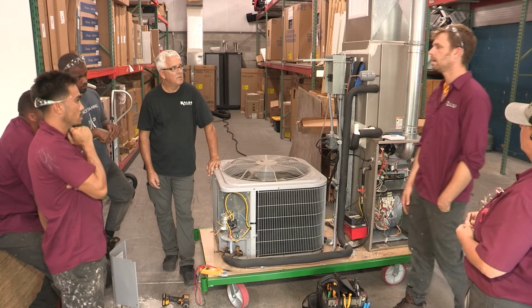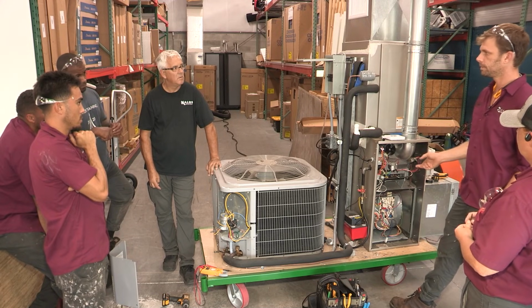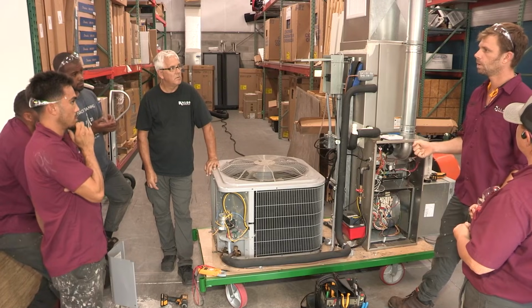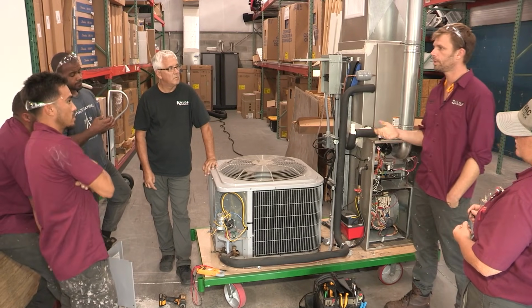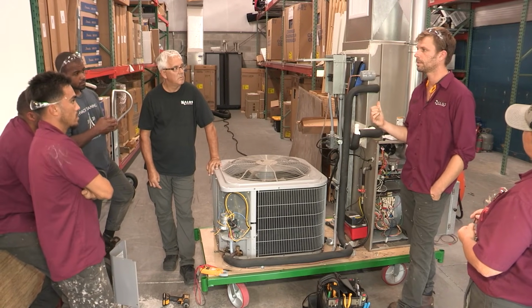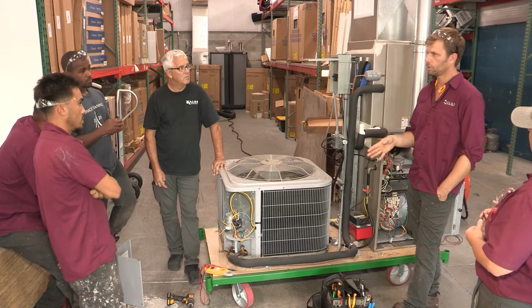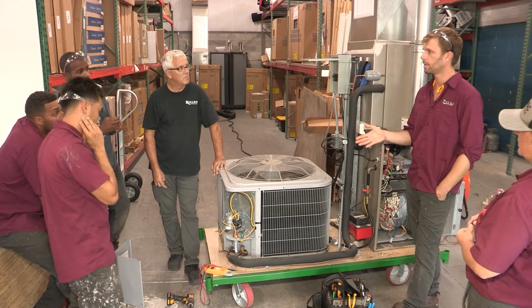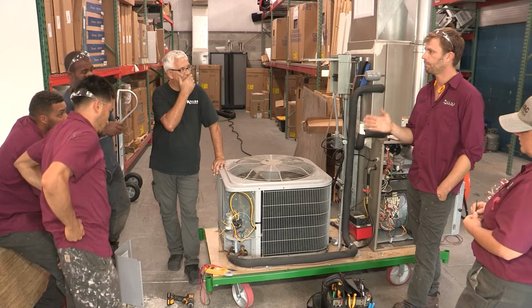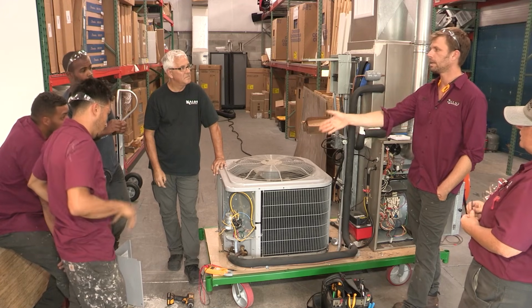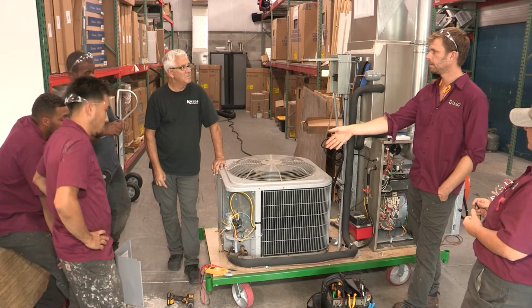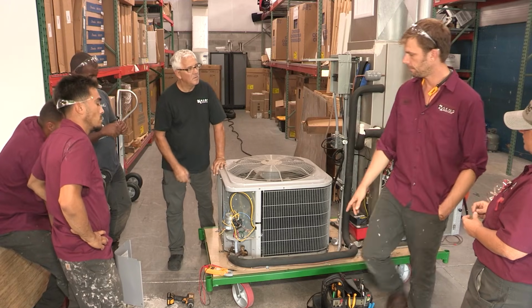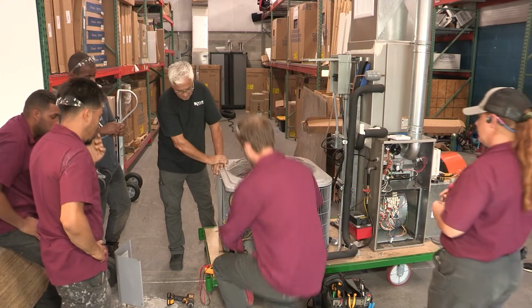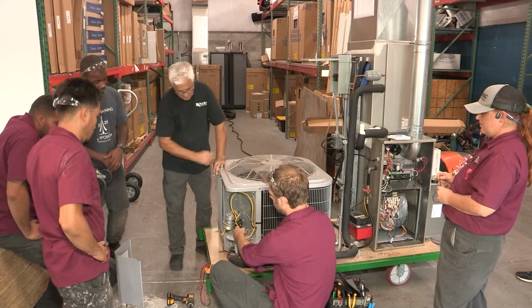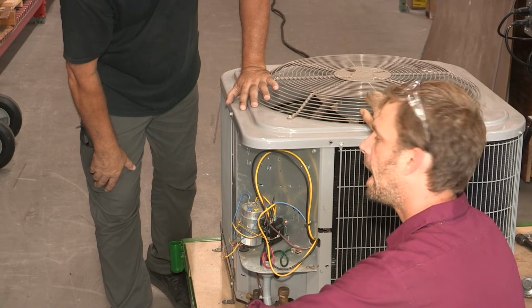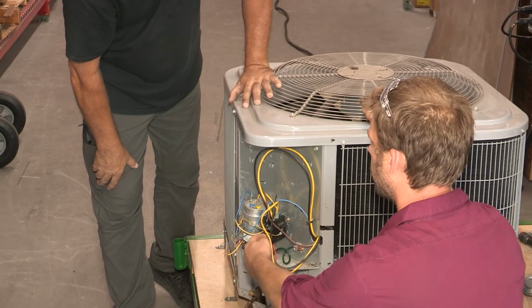But what causes a blown fuse? Short to ground. Overcurrent. So we got too much current. This one was rated for 3 amps. If it's not a connection to ground, like let's say it was rubbed out on ground, that would be a path for the current to take without any resistance, right? The amperage. But if you notice, we already checked common is hooked up to ground and the other side's hooked up to yellow. We do have a path back to ground through the component.